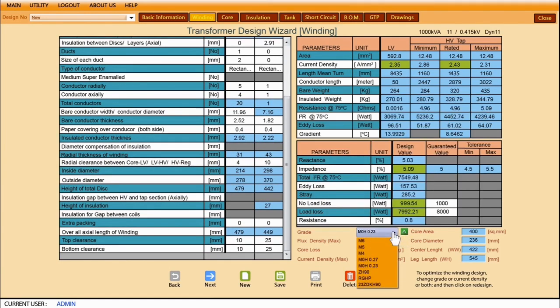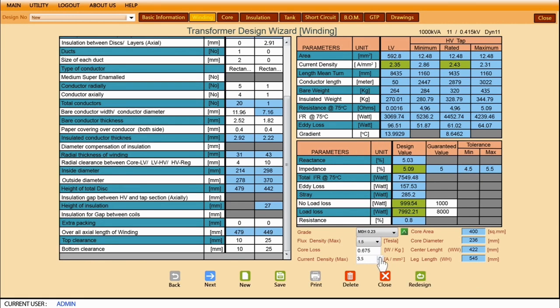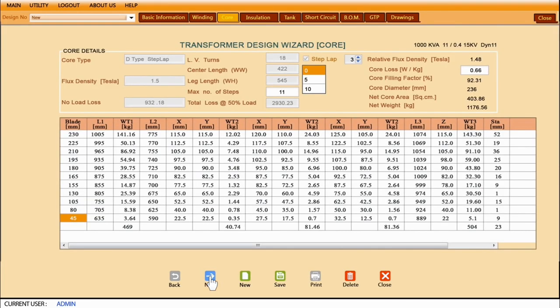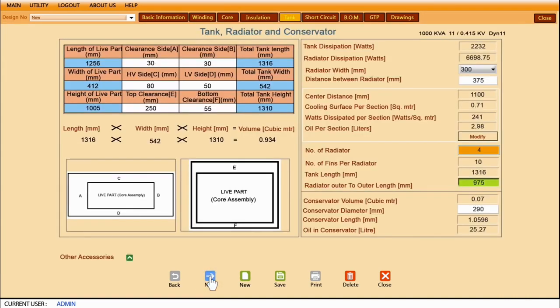You may change the core grade, flux density, and current density as required. TD Pro is intelligent enough to automatically generate core design including core area and net weight of core, etc. TD Pro also shows insulation arrangement between core to LV and LV to HV.